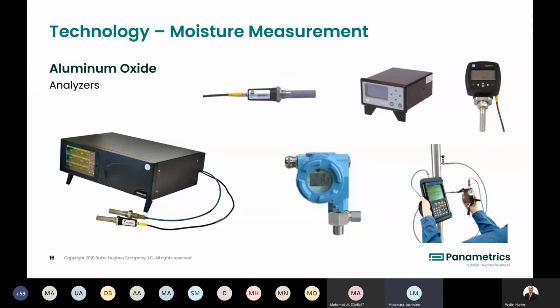So these are the analyzers that those sensors will be connected to. In the bottom left-hand corner, you can see the Moisture IQ. So that's our multifunction, multi-channel analyzer. You can connect up to 6 sensors to that at one time, from 6 different measurement points in your plant or facility, all measuring different processes. And it's got a touchscreen display, communicates over RS-485, Modbus, you have Ethernet functionality, internal data logging, and what you see there is the bench mount version, but you've also got the option of having a rack or panel.